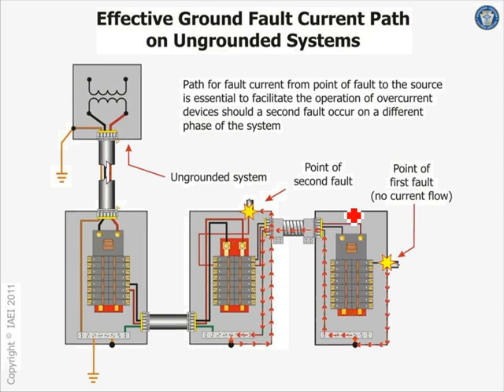You come to a manager and you tell the manager that I will eliminate 85% of the ground faults in your building, and you continue to make canned beef or Ford or cars and so forth. Isn't that a powerful concept? So that's why the ungrounded system is very powerful. The disadvantage of it, though, that you can see, back to your transient, is that when you have a transient or a ground fault on it, it'll create voltage transients that burn electronic equipment. That's the disadvantage of ungrounded systems.